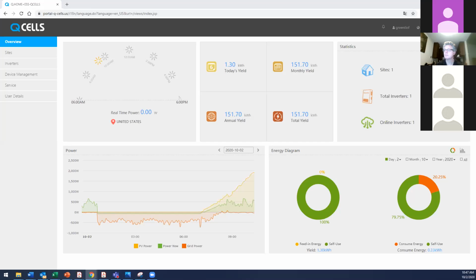That's not the standard, but if you want a special system without any grid connection, we can support that too, and there's nothing additional you need to do since everything is already embedded in the control. There's also a question about working with a different battery. Actually, that's not possible because it's an integrated system. Even though it looks like two separate boxes, our inverter only works with our battery, so it's a full package. We don't only sell the inverter, it can work as a standalone PV inverter if you don't connect a battery or backup panel. But if you want to work with a battery, it has to be our battery, because that's how the certification is. We cannot connect to other batteries, unfortunately.